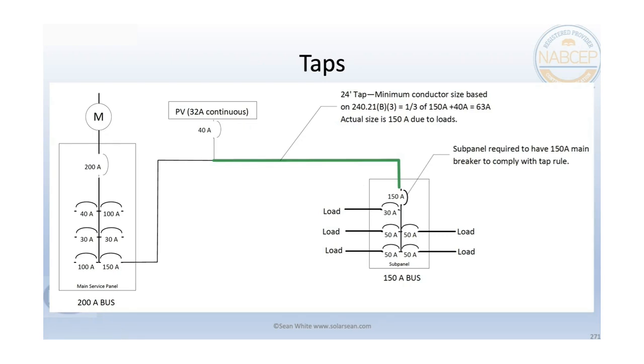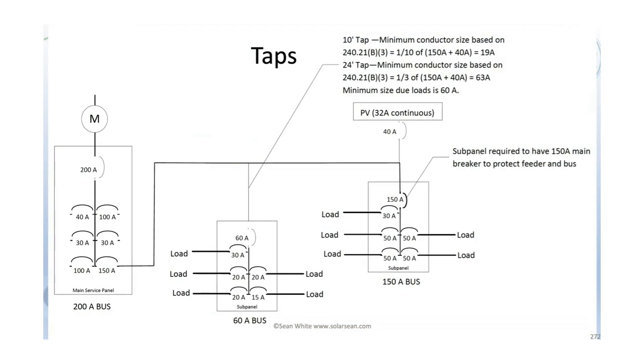Another thing is, we could double check this conductor here. Usually they're not too worried about this conductor, but we would double check this here. But there's the 10-foot tap rule, and they got rid of the 10-foot tap rule and made it the same calculation as the 25-foot in the 2023 NEC. But there's a 10-foot tap rule, and so pretty much if you're going 10 feet, instead of 1/3, it only has to be 1/10, so it would be 19 amps. And so you can see that the 10-foot tap rule probably is never going to even be applied because it's just such a small amount of current. And usually you would be able to satisfy the 25-foot tap rule.